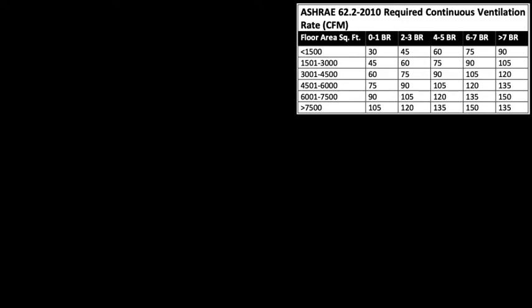Let's do that in terms of equations. So one CFM every 100 square feet, and also 7.5 CFM per occupant. So when we're talking about ASHRAE 62.2, 2010, this is pretty much this.